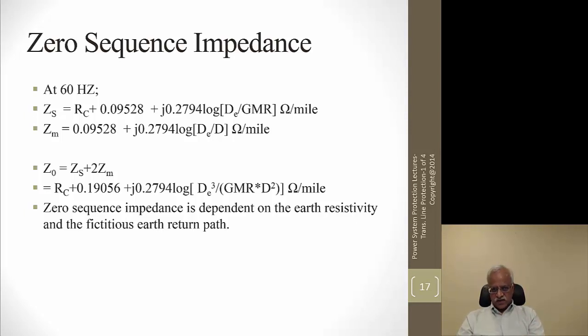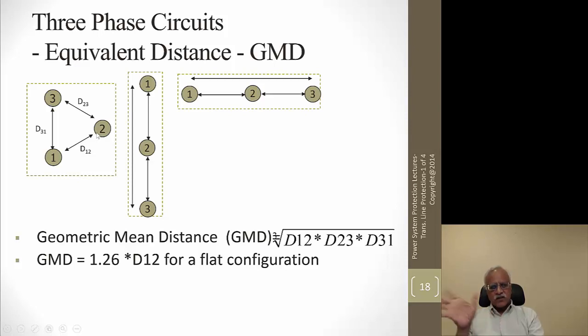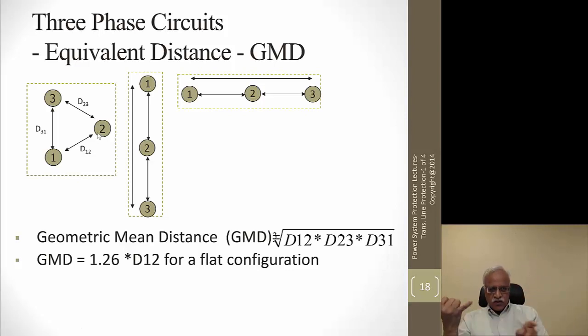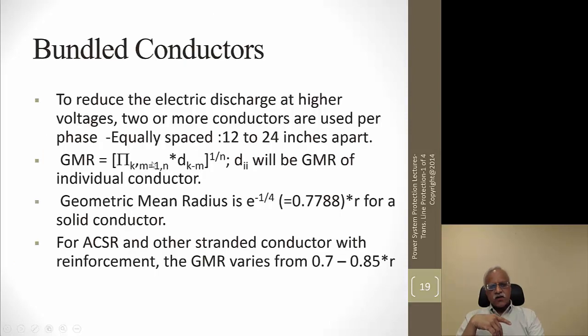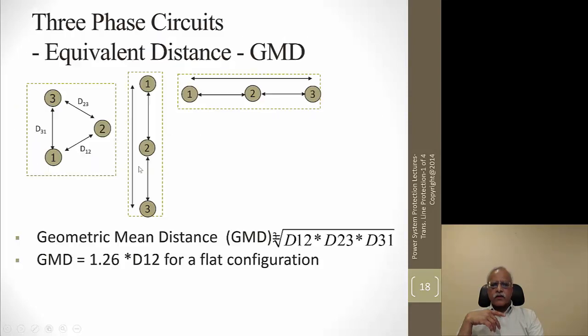These formulas are provided only to verify that the impedance values used for relay settings are reasonable. Phase conductors can be arranged in a delta formation on a steel tower, or in horizontal or vertical configurations. The H-frame structure uses a horizontal configuration, while the tower shown in the GE Alstom reference book uses a vertical configuration.